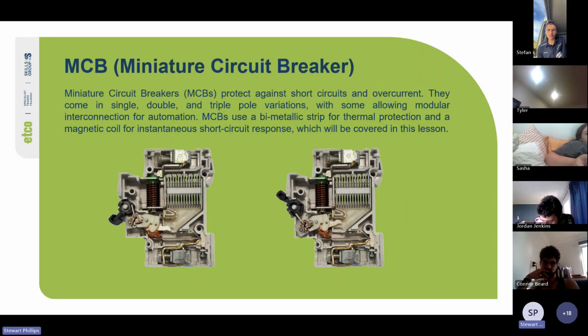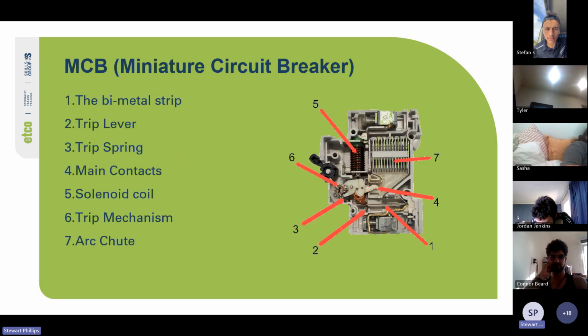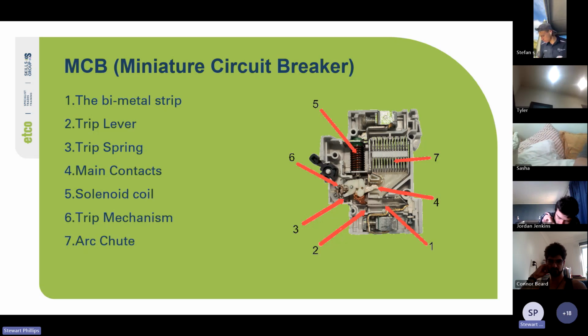Cool. So we've got a side-on view for those you can see, so we'll go through the parts inside. You've got a bimetal strip, a trip lever, a trip spring, your main contacts, the solenoid coil, which also trips the trip mechanism, and you've got an arc chute. There'll be a video talking about the arc chute later. But what it does is if there's an arc between the incoming and outgoing sides of the MCB, that arc will travel up to the arc chute. And because those plates are not electrically linked together, the arc will try and jump across all of those and lose its energy and dissipate.